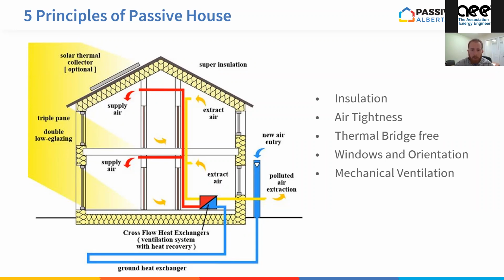A very important part of passive house is to have a continuously running HRV. This is not a North American HRV that runs 20 minutes out of every hour while recovering 40-50% of the latent heat. These HRVs are third-party tested by the Passive House Institute and verified as being 90% or more efficient at recovering latent heat from exhausted air. There are a couple of manufacturers in North America that build PHI certified HRVs, but not many.